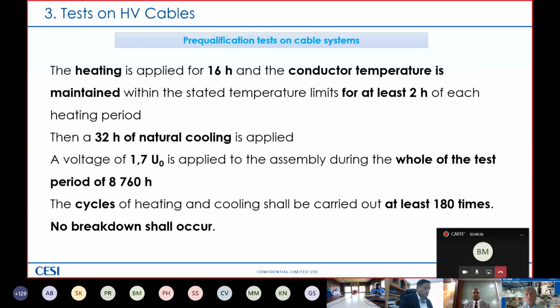Normally, the heating is applied for 16 hours, and the conductor temperature is maintained within the stated temperature limit for at least 2 hours of each heating period. Then we allow 32 hours of natural cooling. We have to apply the voltage at 1.7 U0 for the whole test period. That means 8,760 hours. And taking into account this 48-hour cycling, the cycles of heating and cooling should be applied at least 180 times. During these 180 times, no breakdown shall occur. This is a must.